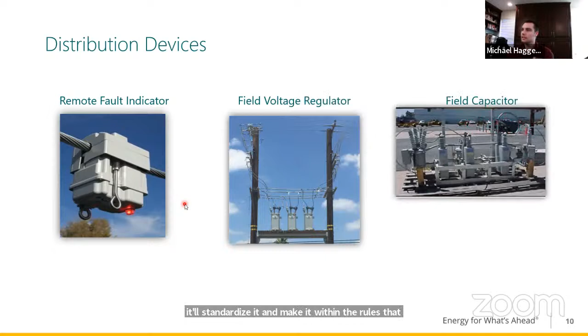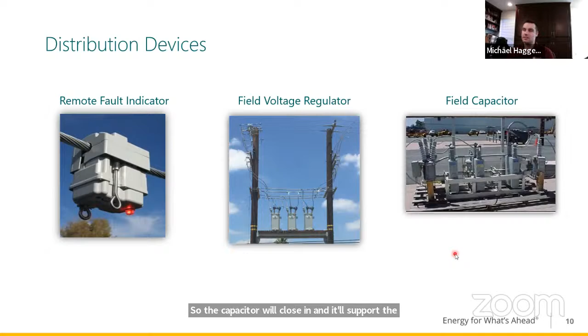Lastly, here's our field capacitor - also a large piece of equipment. When you're looking up on a pole and see little boxes up there, this is also very large. Each one of these little boxes is a capacitor, and they're all banked together. This is actually a switched capacitor, so it doesn't always need to be closed in. During the mornings, there's not too many people running air conditioning, so there's light load, and the capacitor bank will remain open. In the afternoons, on a hot day, everyone turns their air conditioners on and there's a lot more load, so there's a greater need for VAR support. The capacitor will close in and support the VARs on the circuit, ensuring all the power delivered is quality power.